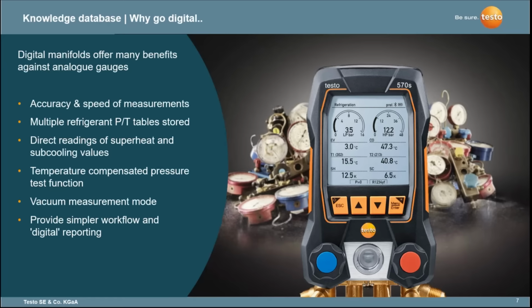These devices link to our Testo Smart app. So with that, you get a second screen mode. You can have the instrument connected to a system and be up to 100 meters away with a smartphone and see what's going on at the instrument. But also when you get to the end of your testing, the readings are documented within the app, and you can then provide a very concise report to the client to show these were the readings that were taken, digital, date stamped, time stamped. It's real proof that obviously the work was completed. So there's many benefits of this move to digital generally from an analog manifold.